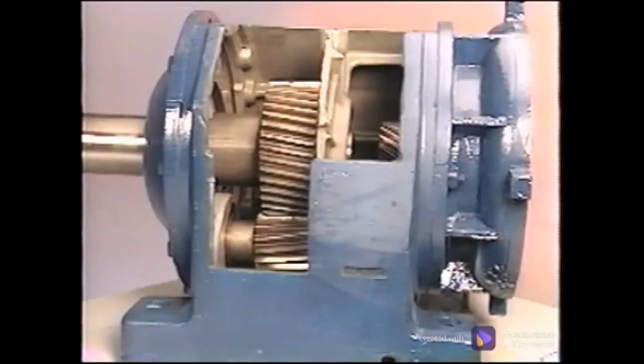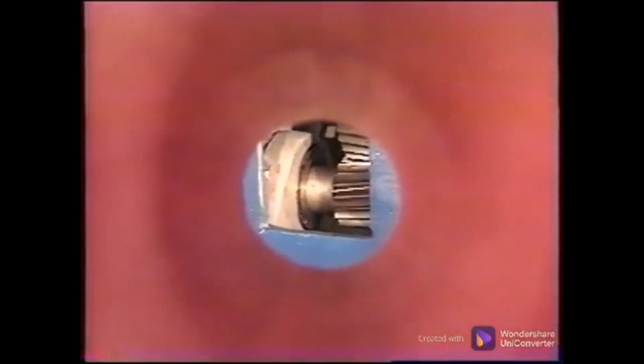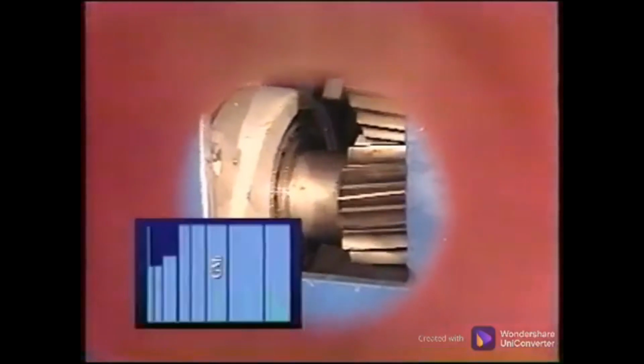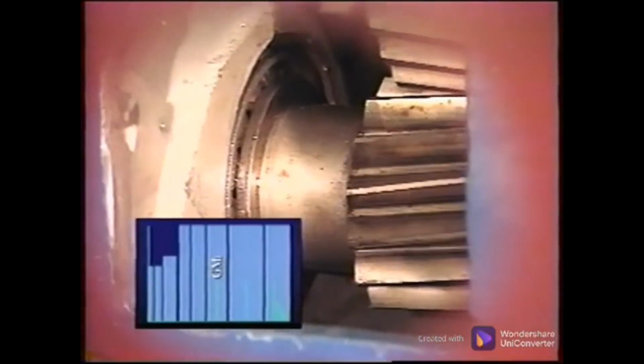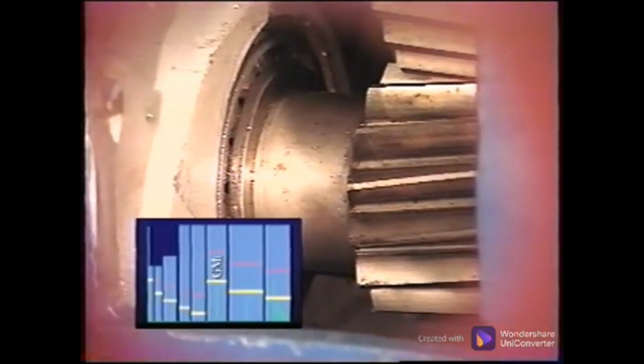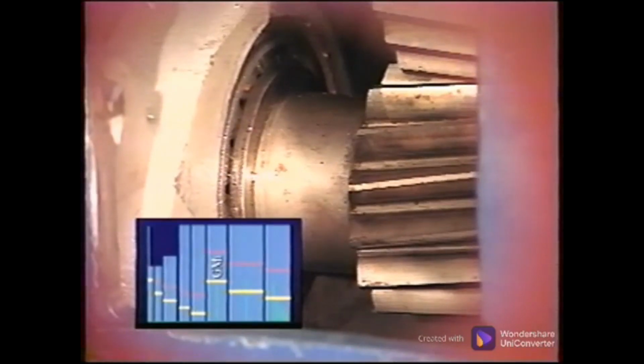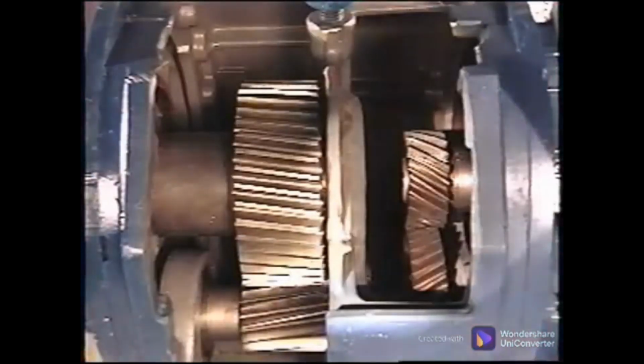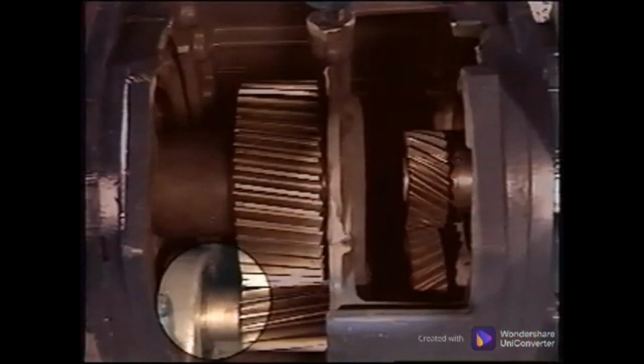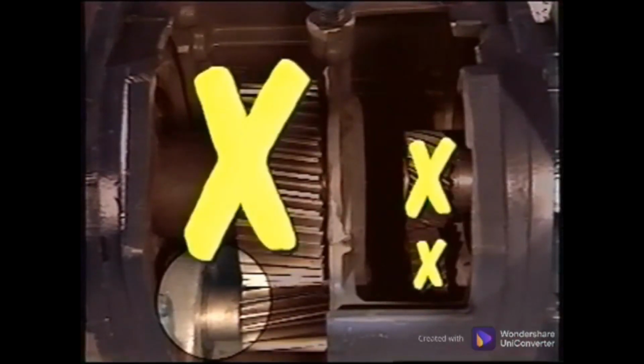When monitoring multiple reduction gear drives, such as this or other complicated configurations, set up the measurement points using tunnel vision. That is, define each measurement point with narrow bands that include only the information you need from that point. The alarms can be set for these individual bands. It is not necessary that the bands form a continuous coverage of the spectral data. Simply define the specific areas of interest that may exclude other gear meshes, other shaft speeds, and other bearings.